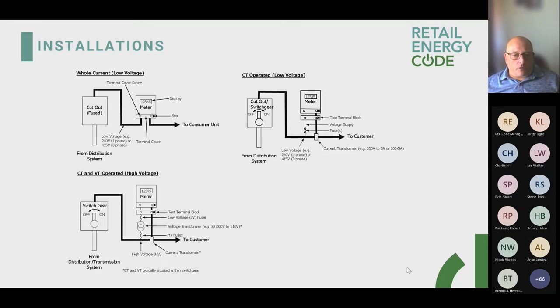When we look at current transformer operated, I'll mention why we start to use that. The maximum that we can put through a whole current system is round about, for domestic, 100 amps. Anything over 100 amp - the maximum size meters that they currently make are 100 amp meters, either 100 amp single phase or 100 amp three phase. Anything over that, we then start to have to look at what we call current transformer metering. If you think of what the size of a 100 amp meter is currently, you could imagine that if I put a 200 or 400 or 600 amp meter in, the size of the meter would have to get bigger because the electronics would have to get bigger, so it would take up more space.